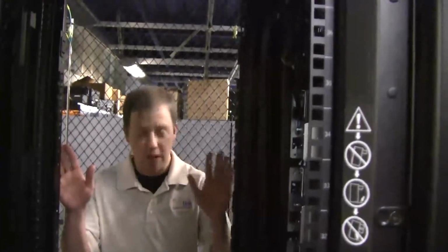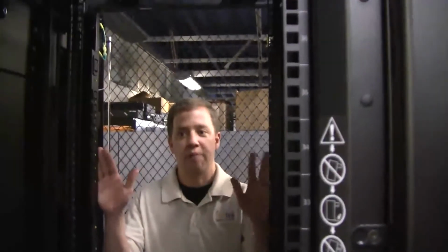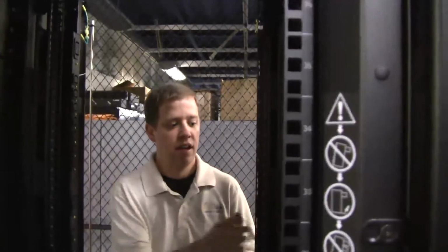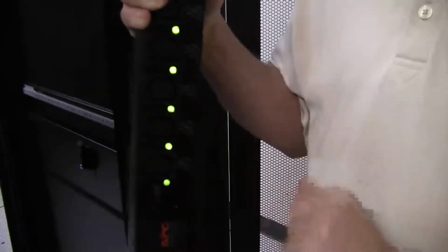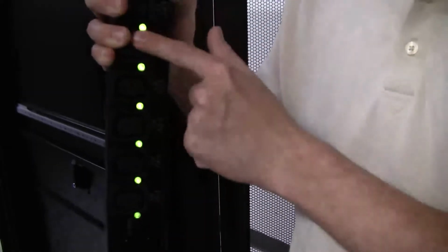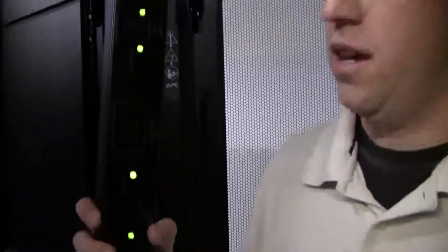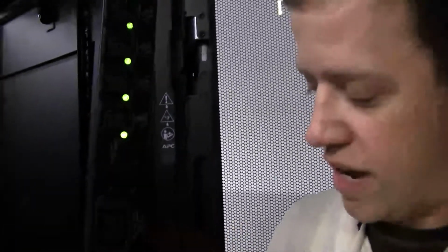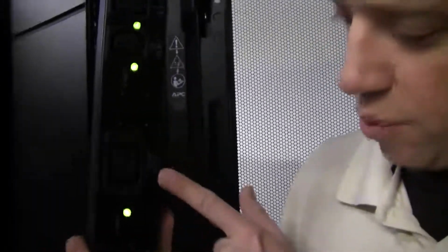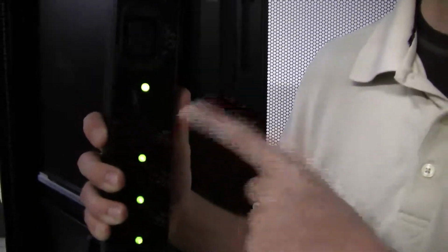This is what a full rack looks like, and here we're looking through an empty one. The A and B solution means you have power from one PDU and another, basically power from an A UPS and a B UPS. Each power strip is IP addressable, so you can plug an Ethernet cable into it, connect it to your switch, and turn off individual ports one at a time. You can see they're labeled like L2-3, for port 9, port 10, port 11, and you can go in and turn off a specific port remotely.